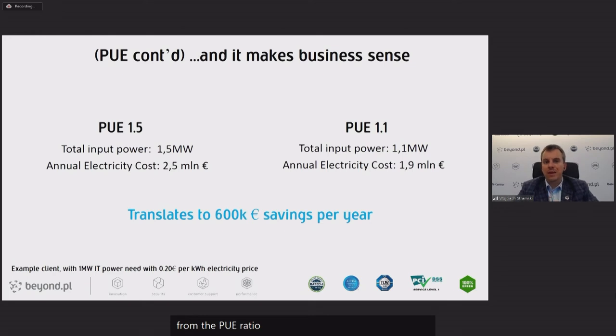PUE also makes sense from a business perspective. A customer that requires 1 megawatt of IT load can save 600,000 euros per year, assuming an energy price of 20 eurocents per kilowatt hour, which is actually quite low when you look at where we are today on the global map of energy prices, just by drawing from a data center that has a PUE of 1.1 versus one that has a 1.5.